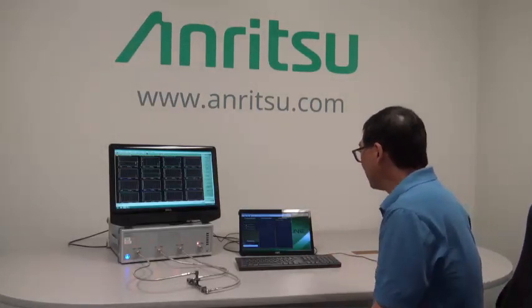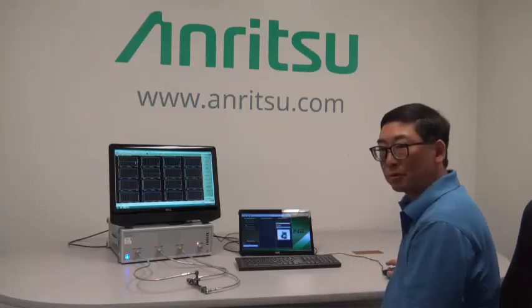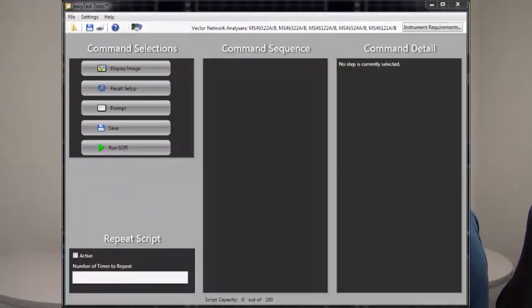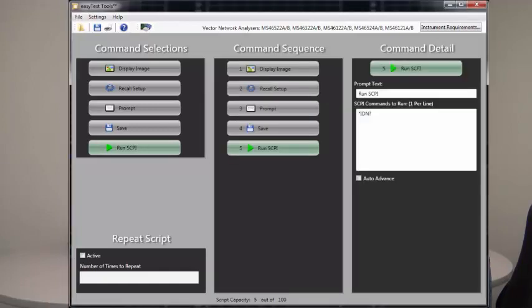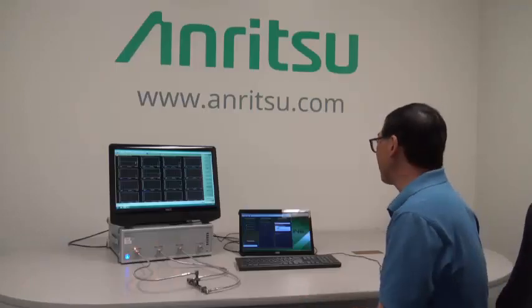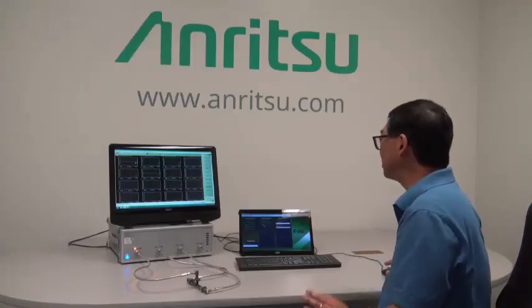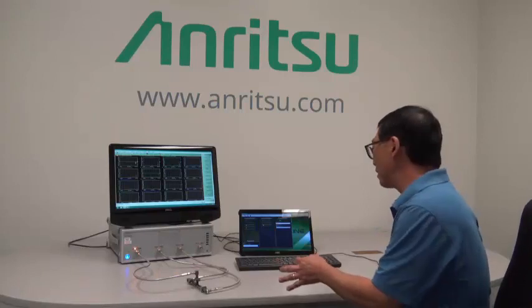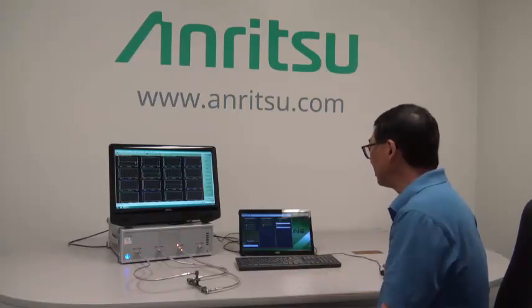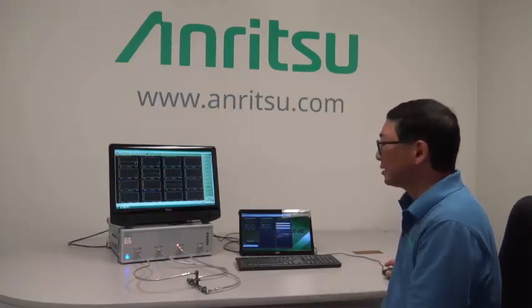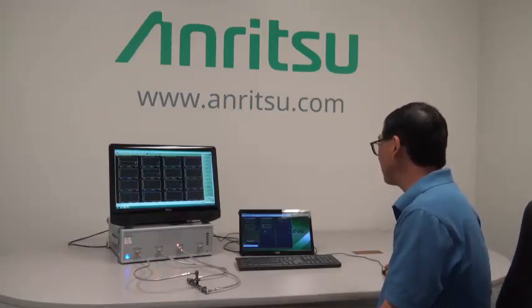It's a drag and drop operation that puts different command selections into the sequence. You can display images, recall different setups, prompt the user to do certain things, connect devices, run different cal steps along the way, save files, save data, as well as run SCPI.